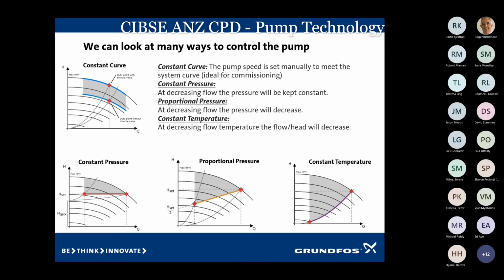Why we would use constant pressure in smaller runs is because of the valve authority. This way, when using constant pressure, we're still maintaining a good pressure, but we're still reducing the pump speed to match the demand. If we go to proportional pressure to the right, you can see now, as I reduce the speed, I drop my head and I drop the flow rate at the same time. So we are now pulling our energy down even lower because that pump's running at about 65%. So that's quite a bit of energy pulled down.